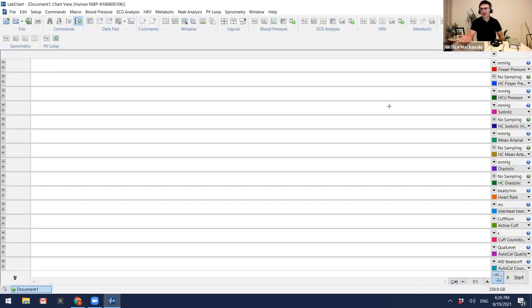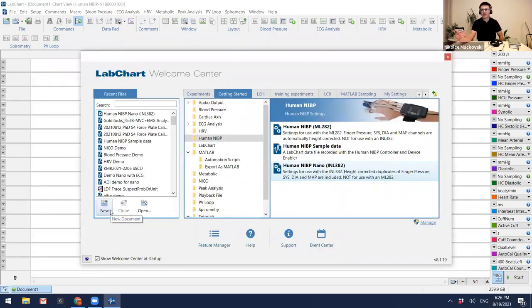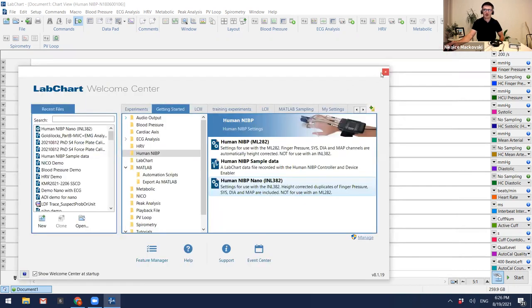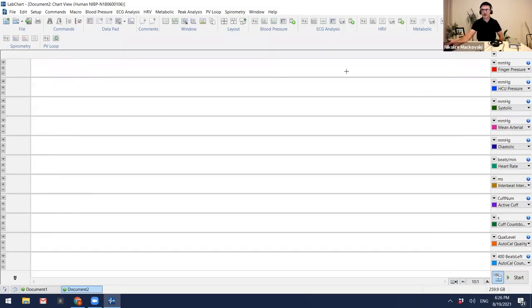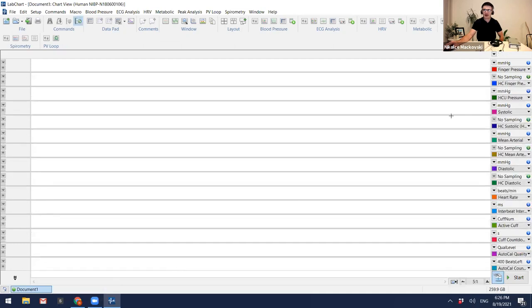Now we have quite a few channels here. We have a few doubling up channels. The reason why is because the HCU is there as a correction factor for any time I move my hands. So I would recommend this settings file if you're moving your arms around. If the subject's staying stationary and not moving, then what you could do instead is just go to Home and click on New, and it'll show you not as many of the files. So for example, if I click on New instead of the settings file, now you can see there's less files here. You can actually see there's HCU pressure, but I don't have the HCU correction for the rest of the files. But that's something I think is important to have. Yes, it's more channels, but that way you can have a better representation of what the finger pressure is based off the HCU.